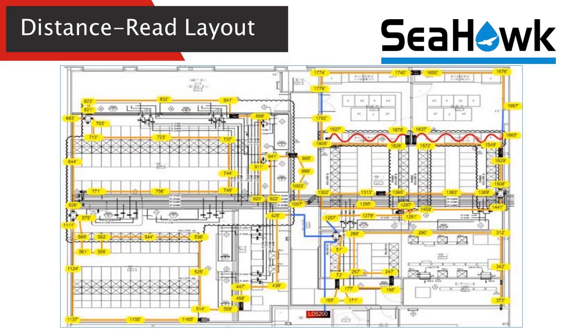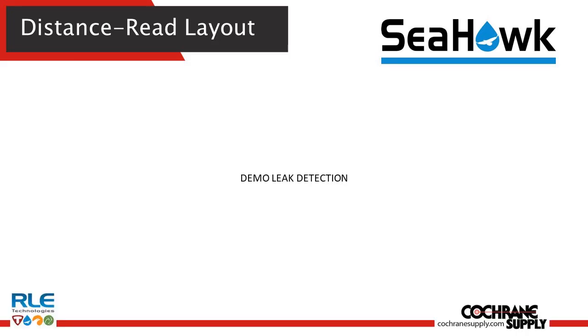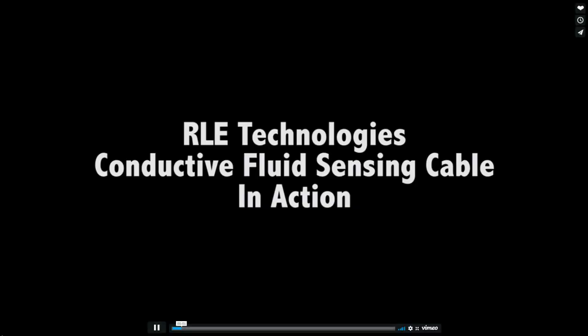And then when you go through all of the commissioning process, as you put a damp rag along the sensing cable, you're going to go ahead and identify different distances that all get recorded into that commissioning and programming process. So now here is an example of what a distance read leak controller will look like when it alarms.